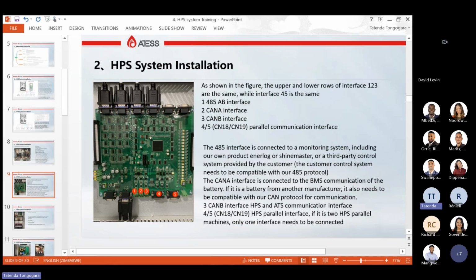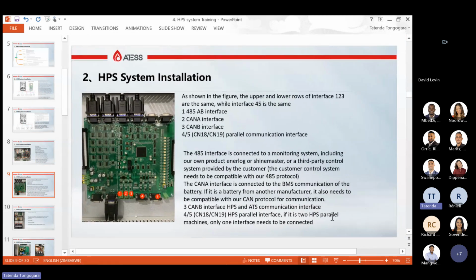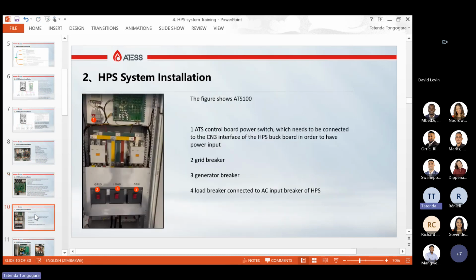So if you are using a battery, most local batteries are compatible with our system, but we just need to find out if the communication protocol is compatible with our CAN A. In the event that you're using Pylon Tech batteries, if you enable your BMS, you set it to 2. If you're using Pylon Tech or all batteries under the Pylon family, you contact one of our support team or the in-house support team. They can help you. It's not difficult. It's just changing the BMS communication enable value. That's the only thing you change.